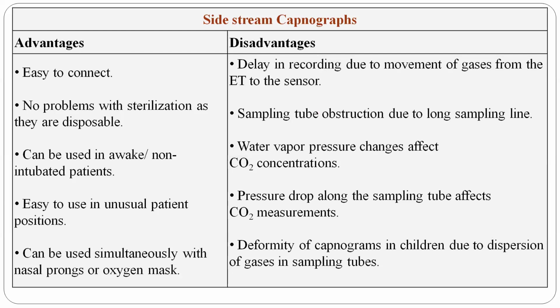Disadvantages: there is delay in recording due to the movement of gas from the ET tube to the sensor, sampling tube obstruction due to a long sampling line, water vapor and pressure changes affect carbon dioxide concentration, pressure drop along the sampling tube affects carbon dioxide measurements, and deformity of capnograms in children due to dispersion of gases in the sampling tubes.